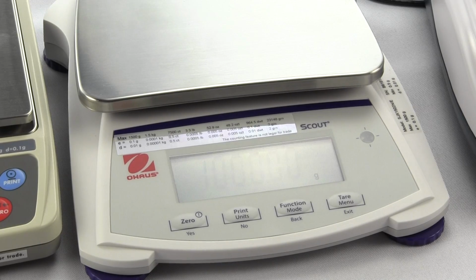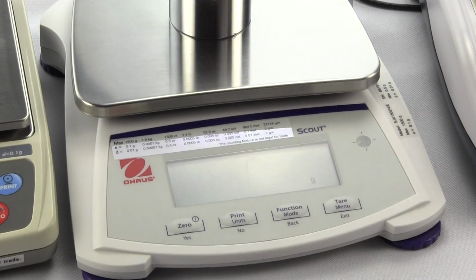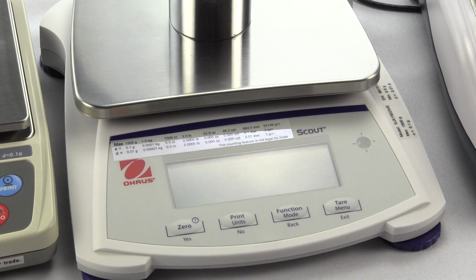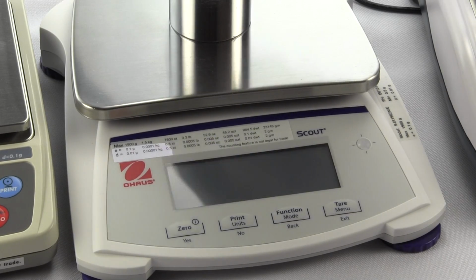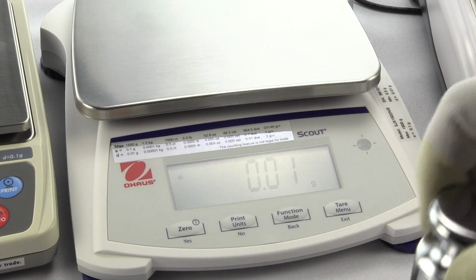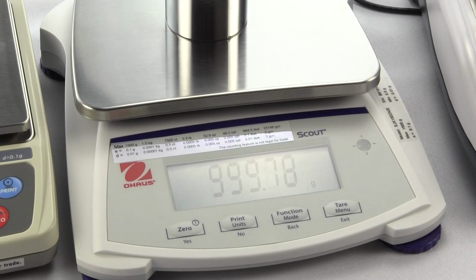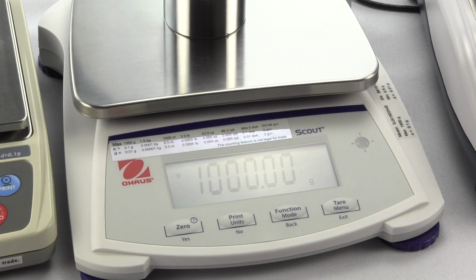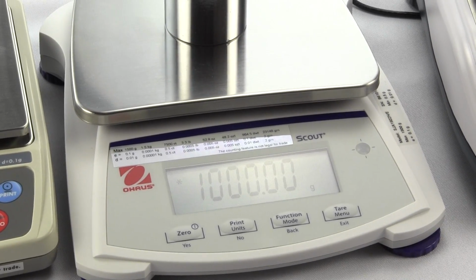So now we have to. It's flashing. I have to put my 1000 on. You'll see the C. It's storing that value. It's done. Take my weight off. Put my weight on. It's calibrated. This is the one I had to show you. It's a little bit more difficult to do the calibration.